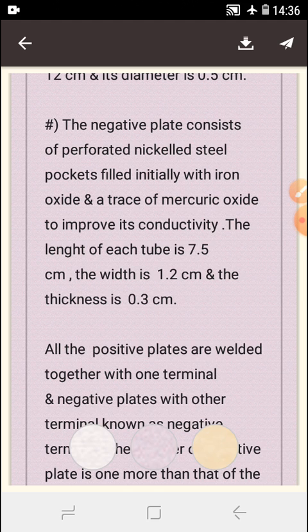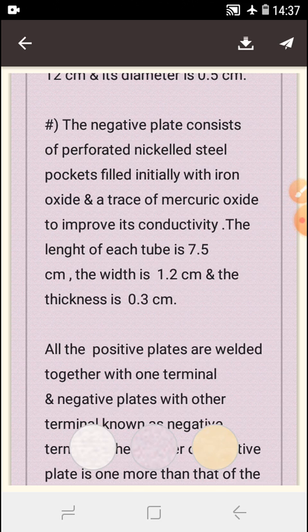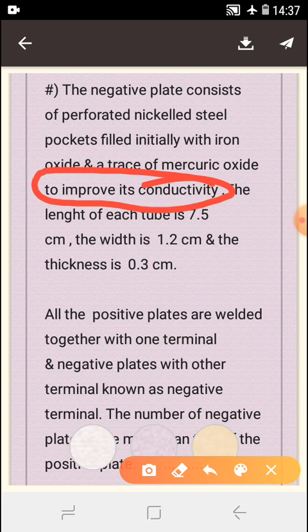The negative plate consists of perforated nickel steel pockets filled initially with iron oxide and a trace of mercuric oxide to improve its conductivity. The length of each pocket is 7.5 centimeters, width is 1.2 centimeters, and thickness is 0.3 centimeters.